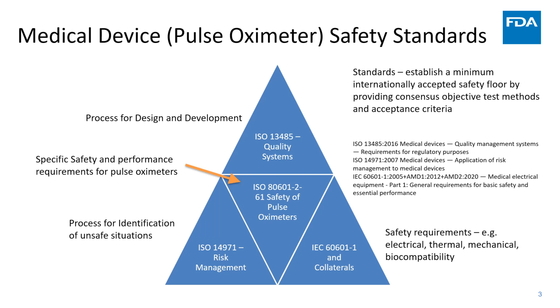Now, we also need to talk about the differences between what an engineering standard is and what a clinical perspective or clinical standard might be. The standards that we are dealing with within ISO are device construction standards. You can see over here in the pink, this is what our scope is, right? Is the device safe? And for terms of art, we define safety as basic safety, safety from physical hazards, and essential performance. Does your device perform in an acceptable way? But importantly, that's asking because I need to test my device and I need to know how badly certain functions can behave and still be acceptable, right? That's not applying it to the patient and saying, is a 3 or 4% change in saturation good enough? That is not what our engineering standard is about.